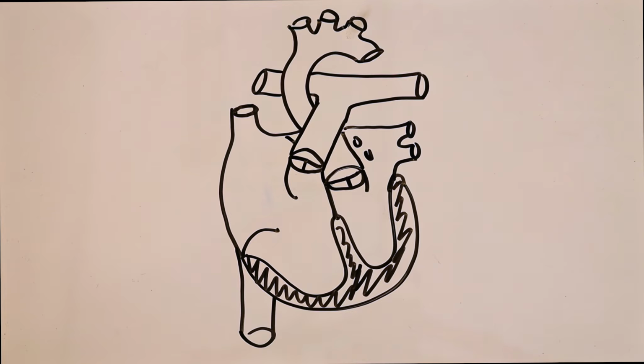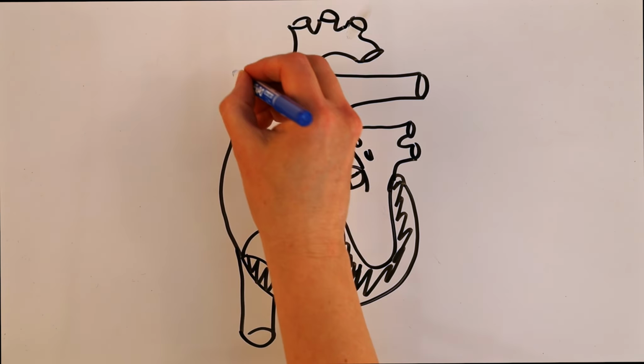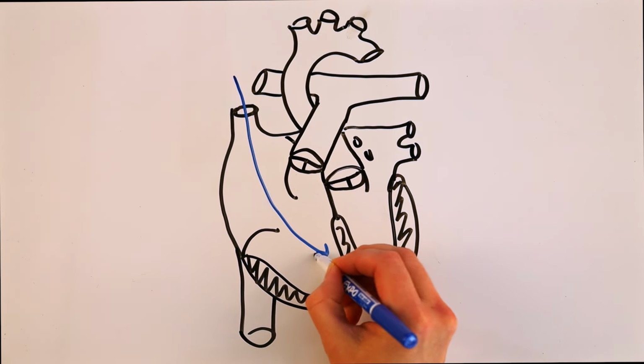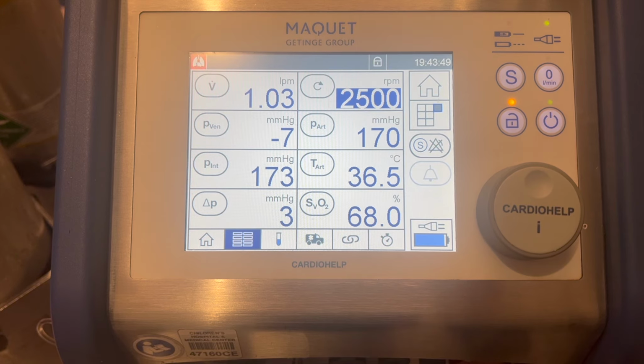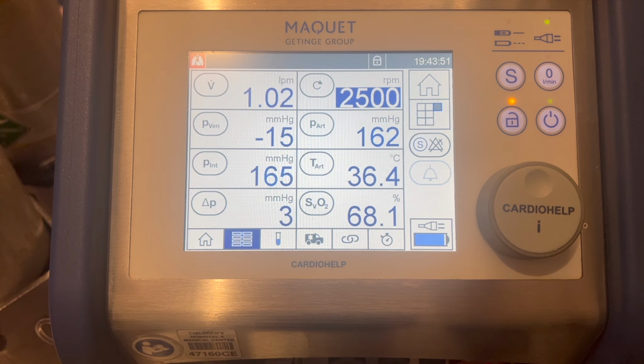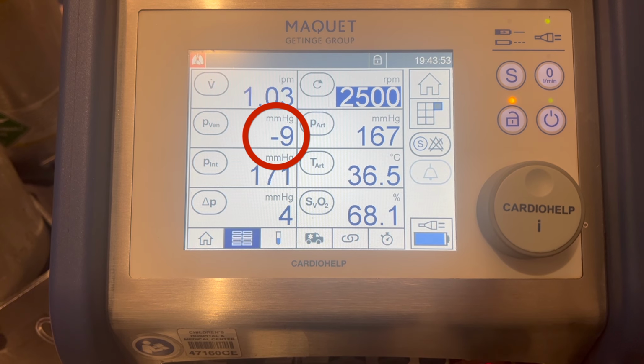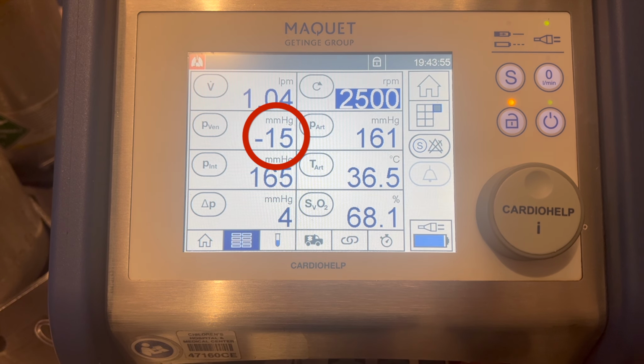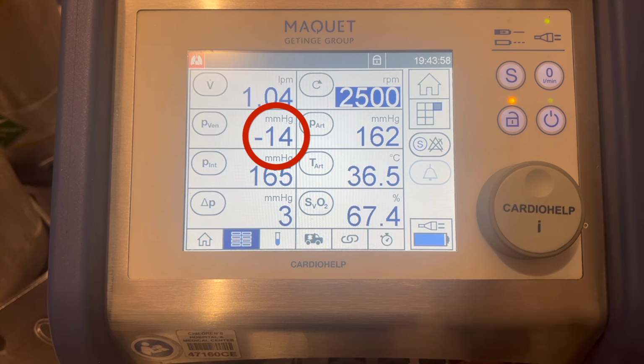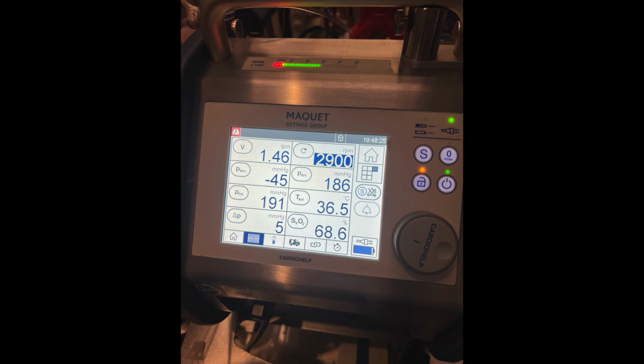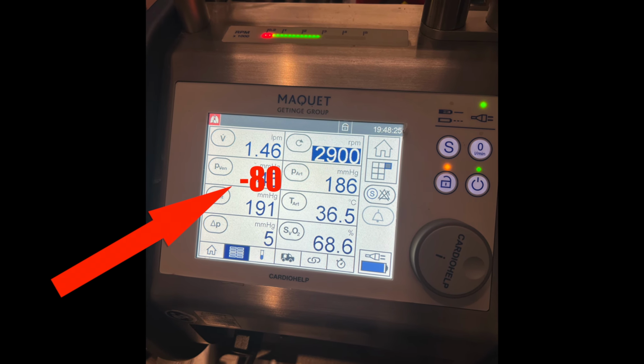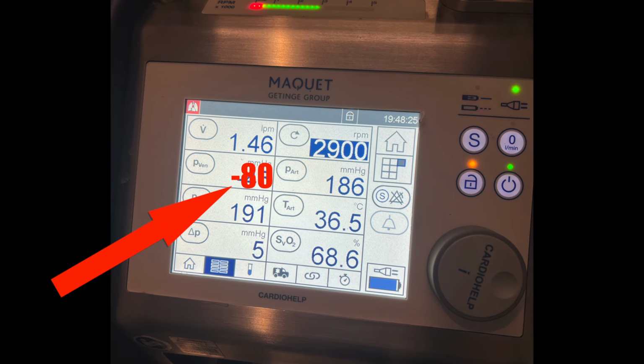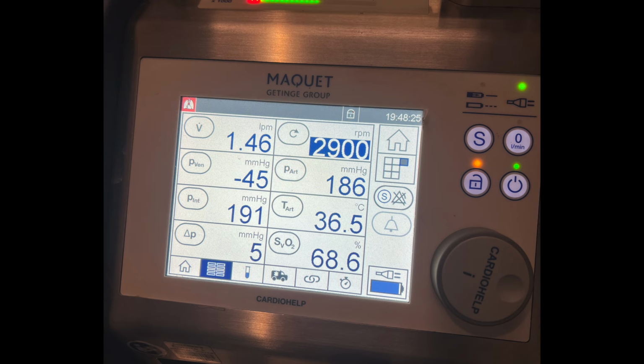For the heart, preload is the volume of blood returning to the ventricle, which often is impacted by the central venous pressure. Same with the pump. While spinning, the pump generates a negative pressure to pull blood into it. There is a limit to how much negative pressure it can safely generate. Too negative of a pressure, and blood can start to hemolyze, or it can suck the walls of the atrium into the outflow cannula. To stop this from happening, the pump will slow down or even stop if the pressure becomes too negative, dropping the output provided by the machine.